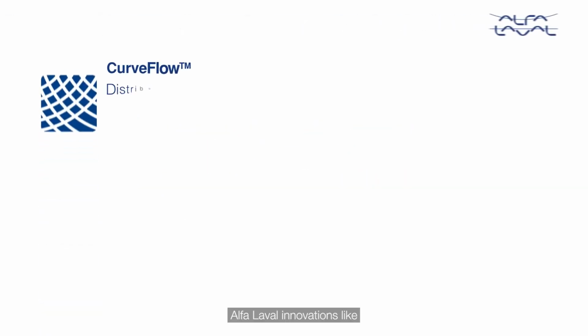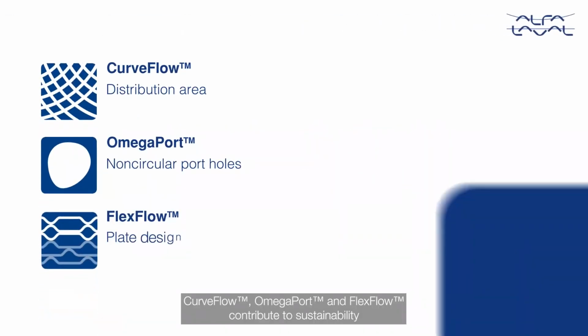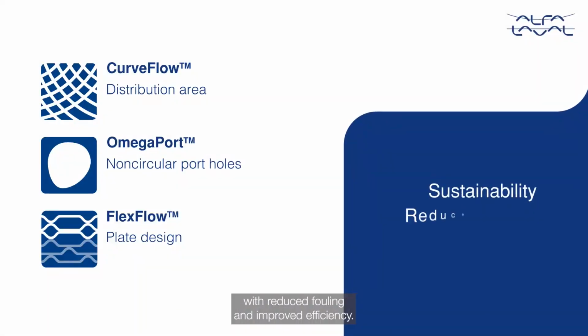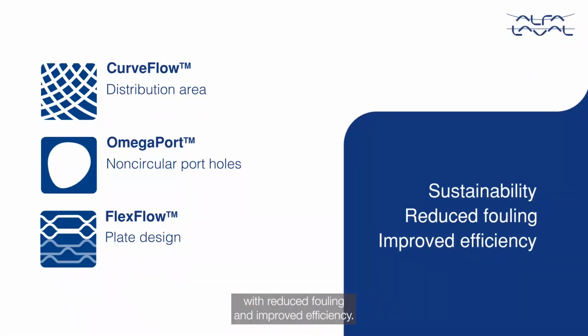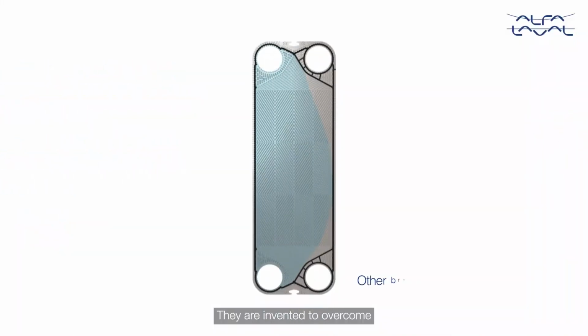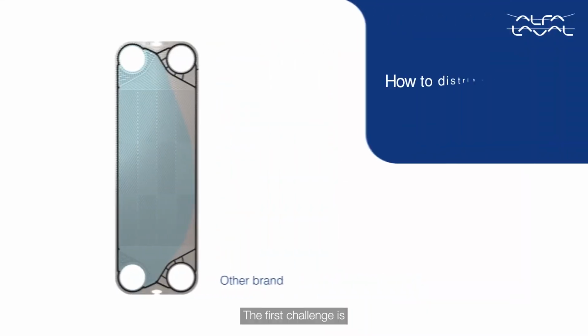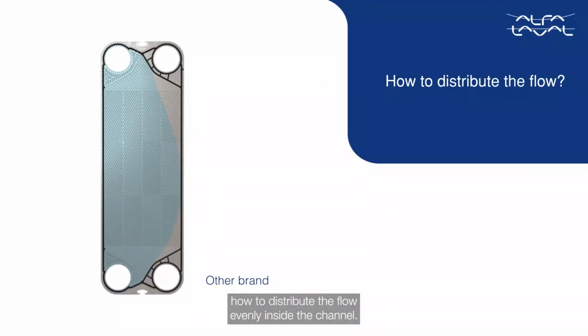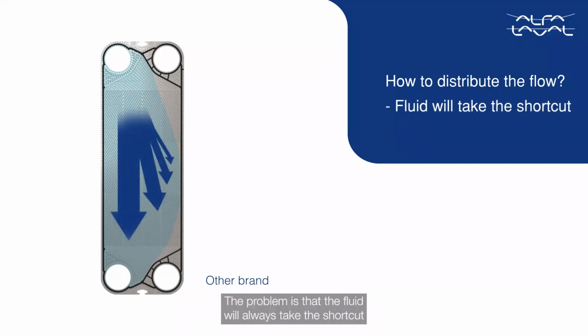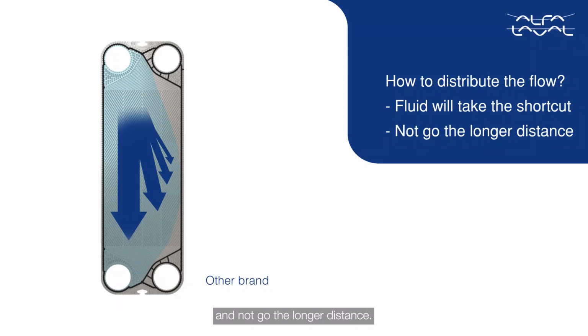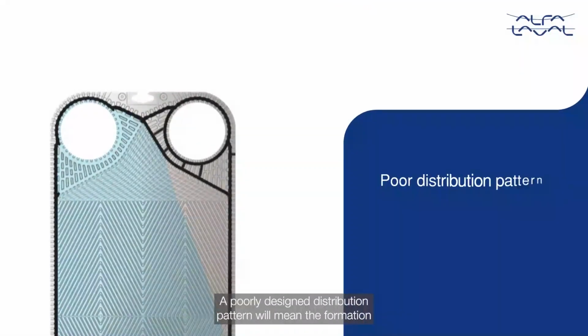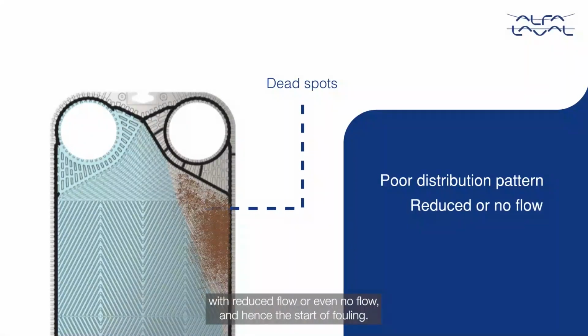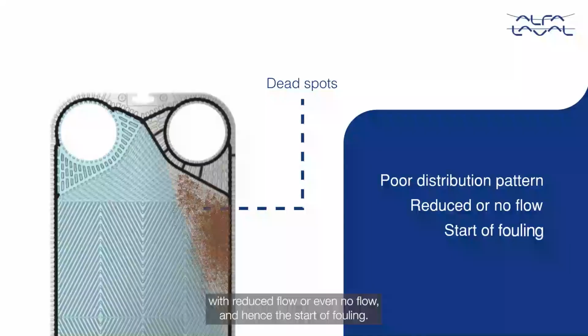Alfa Laval innovations like CurveFlow, OmegaPort and FlexFlow contribute to sustainability with reduced fouling and improved efficiency. They are invented to overcome the common challenges for all plate heat exchanger manufacturers. The first challenge is how to distribute the flow evenly inside the channel. The problem is that the fluid will always take the shortcut and not go the longer distance. A poorly designed distribution pattern will mean the formation of dead spots with reduced flow or even no flow, and hence the start of fouling.